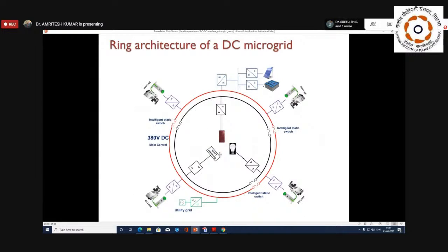And for feeding the local loads, nowadays we find so many appliances that are based on DC itself. It's not required to plug into 230 volt. It can work on the DC. So 48 volt DC is the standard that is being kept for varied types of load, like refrigerator, light load, and many consumer loads are also compatible with 48 volt. Nowadays we are having EV chargers, that's your e-rickshaw, that is also being charged at 48 volt. So this is one standard that people think of using.